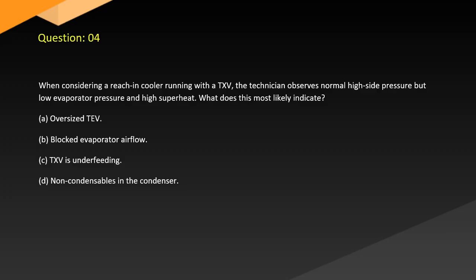Question 4. When considering a reach-in cooler running with a TXV, the technician observes normal high side pressure but low evaporator pressure and high superheat. What does this most likely indicate? A. Oversized TEV. B. Blocked evaporator airflow. C. TXV is underfeeding. D. Non-condensables in the condenser.